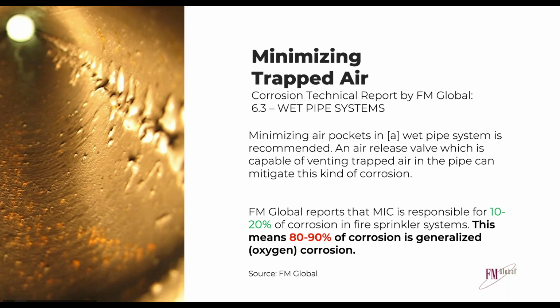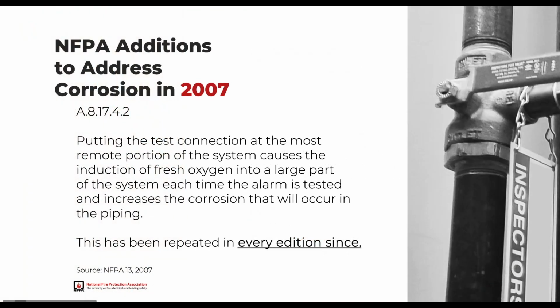well, they did a long-term study first concerned with MIC (microbiologically influenced corrosion) in sprinkler systems, and they came back and said that they felt MIC was responsible for 10 to 20%. Well, if that's the case, then the other corrosion, 80 to 90%, is being caused by oxygen-related corrosion. So let's do whatever we can to get air out of a system. The industry started to address this in NFPA code changes, first by allowing the remote inspector's test, which was there to test all the bells and whistles of a sprinkler system, where it used to be recommended to be put at the farthest point of a system. They were allowing it to be relocated back to the inlet of a system, so you would not introduce more new oxygen into the system.